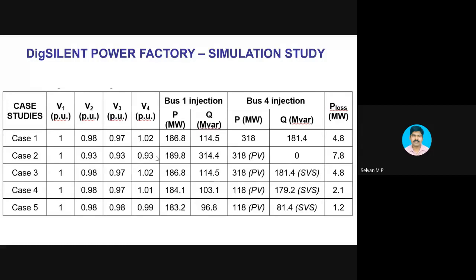In power system, a voltage below 0.95 is considered to be an undervoltage. You cannot have that. It is not a healthy system. So what happened? Why has the voltage reduced? It is because the total reactive power requirement, even though it is met, is coming from bus 1. The reactive power has to travel through many long transmission lines, which causes this voltage drop.